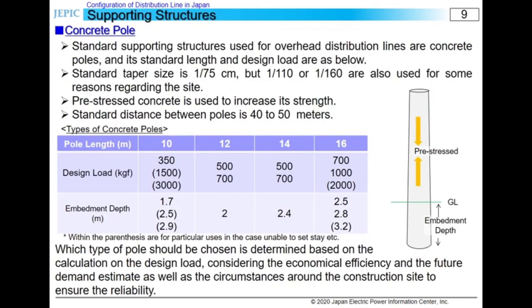First, I'd like to talk about the concrete pole, which is the main supporting structure of overhead distribution line. The table shows the standard types of concrete poles in Hokuriku area. The most commonly used pole is 14 meters long.